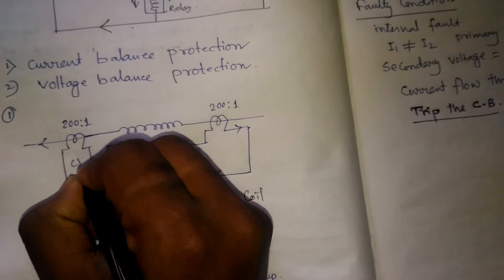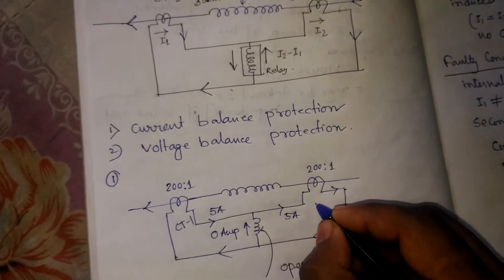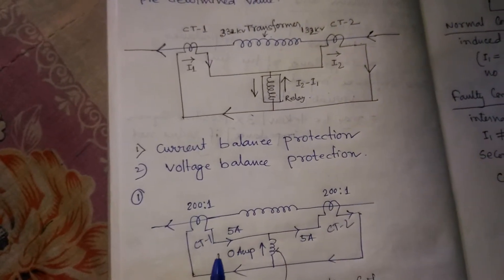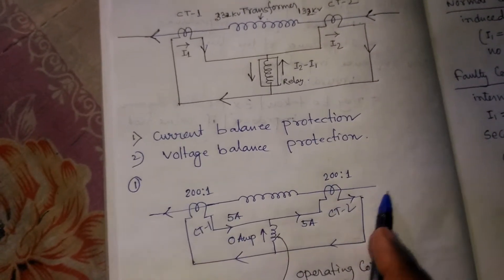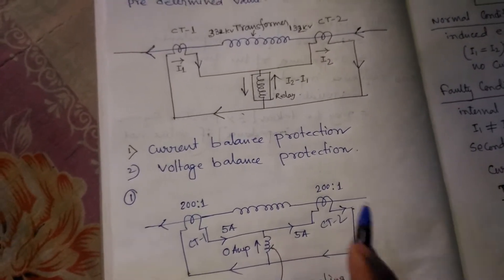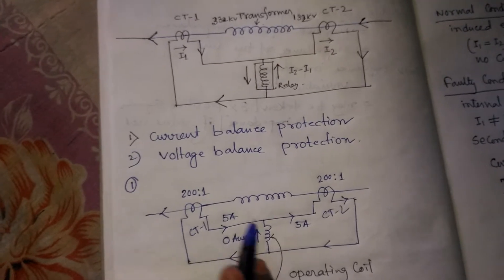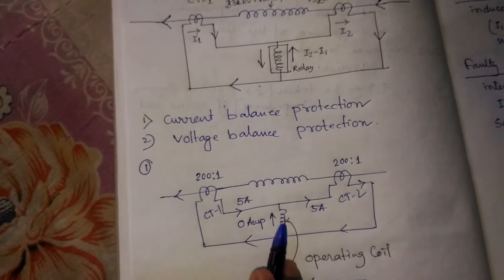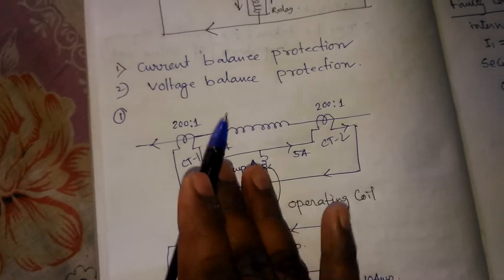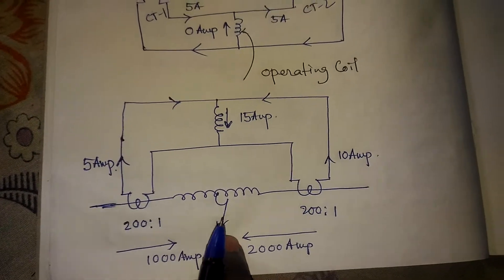The current flowing from CT1 is 5 amperes and the current flowing from CT2 is also 5 amperes. So the I2 minus I1 current is zero — zero current is flowing to the operating coil of the relay, so the relay will not operate.